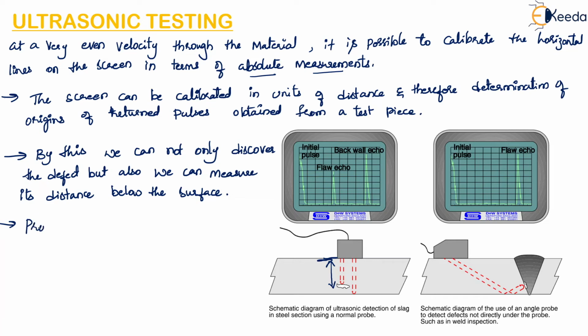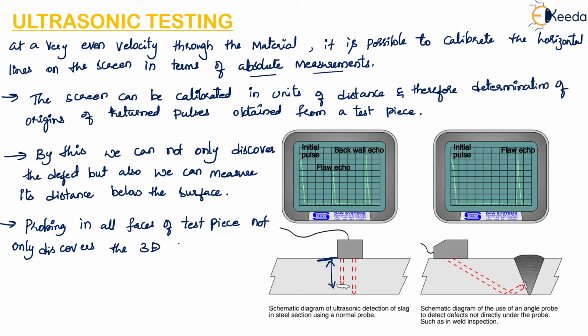So probing in all faces of the test piece not only discovers the three-dimensional, I'll just write it as 3D defect, and measures its depth, but can also determine the size of the defect.